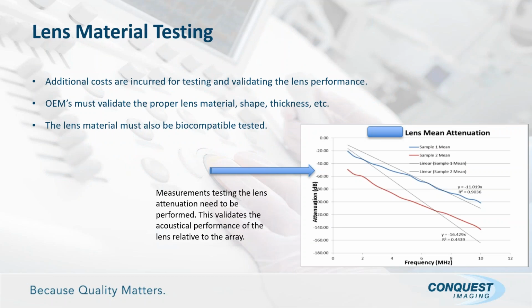I mentioned earlier a little bit about the lens testing. Again, I don't think a lot of people realize what goes into just making the lens. Obviously, we all see it on the probe. It's what touches the patient, etc. But the actual design of those is a lot more complicated and a lot more detailed than you think. Even from a repair standpoint, we go through a lot of testing and validation just to replace a lens, because we have to make sure it's biocompatible and not changing the acoustic output. So when you are on the array design side and you're designing this array, if you put a crappy lens on there, you may have the world's greatest array that you could just put on somebody's head and scan their entire body, but if the lens is bad, it essentially becomes worthless.